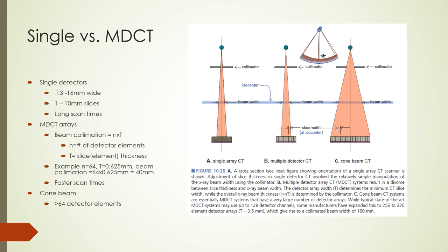In multi-detector CT scanners, slice thickness is determined by the detector configuration, represented by the number of detector elements and the thickness of each element. Beam collimation equals element thickness multiplied by the number of detector elements. For example, 64 detector elements each 0.625 mm thick gives a beam collimation of 40 mm. Once you have more than 64 detector elements, the beam profile becomes more like a cone — called cone beam CT.